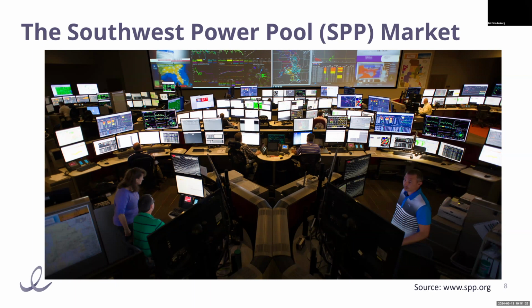All of the battery installations are responding to signals as quickly as 250 milliseconds, a quarter of a second. They're already moving in very good unison because it's power electronics, as opposed to the governor on a rotating thermal generator. So we get really good responsive capabilities.